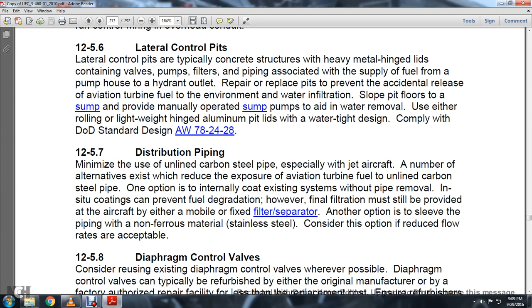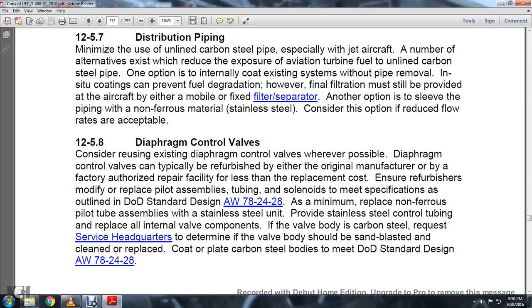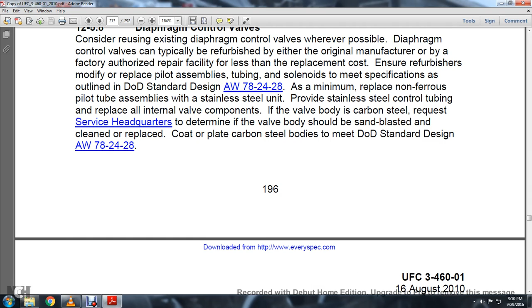12.5.8 Diaphragm control valves. Consider reusing the existing diaphragm control valves whenever possible. Diaphragm control valves are typically refurbished by the original manufacturer or a factory authorized repair facility for less than replacement cost. Ensure they are refurbished or modified to replace the pilot assembly tubing and solenoids to meet the specification outlined in Department of Defense AW782428. The minimum replacement is a non-ferrous pilot tube assembly of stainless steel. Components of the carbon steel valve body require service. The valve body should be sandblasted, cleaned, and recoated, and the carbon steel bodies should meet the Department of Defense design AW782428.